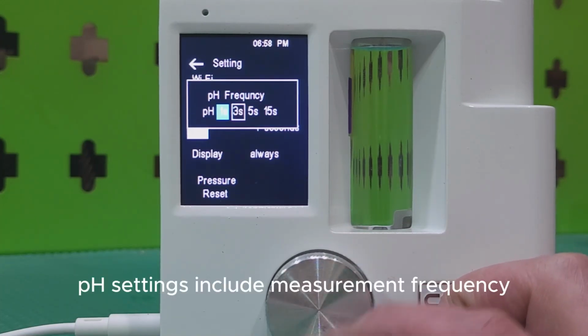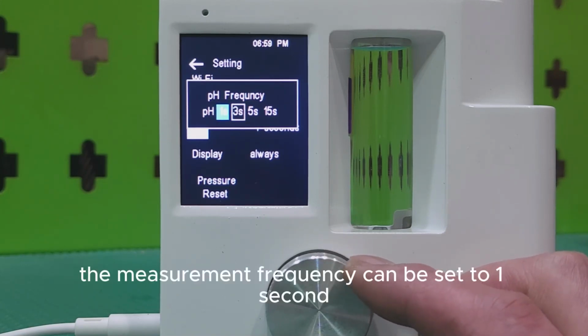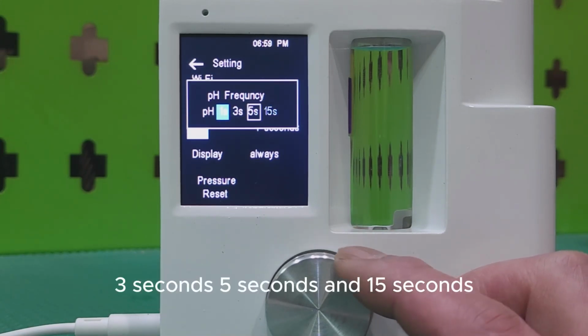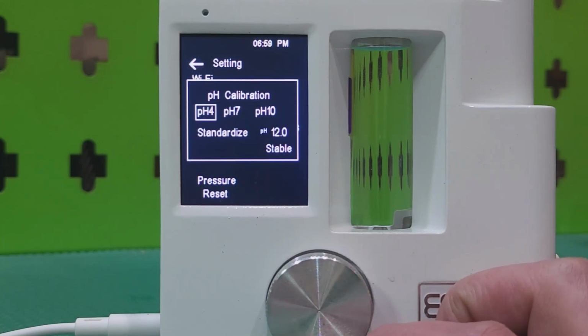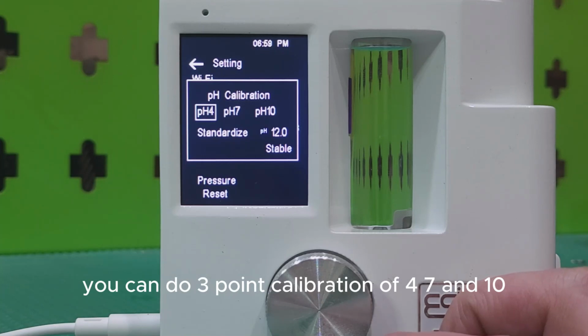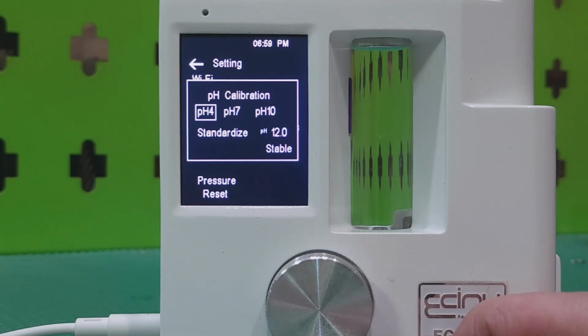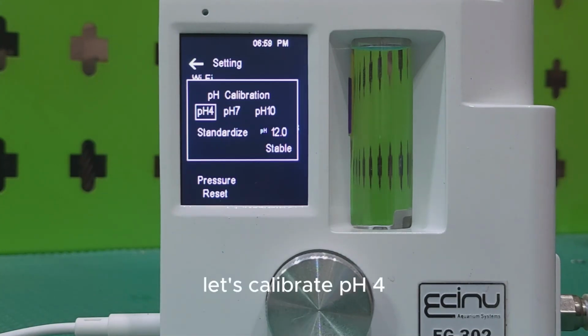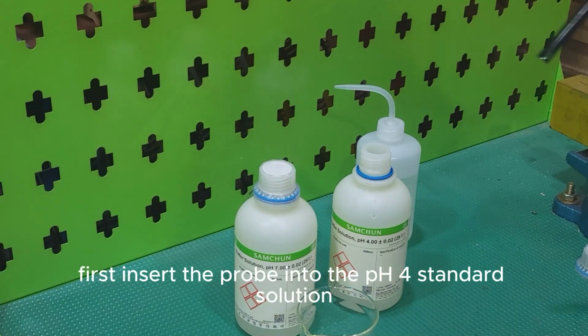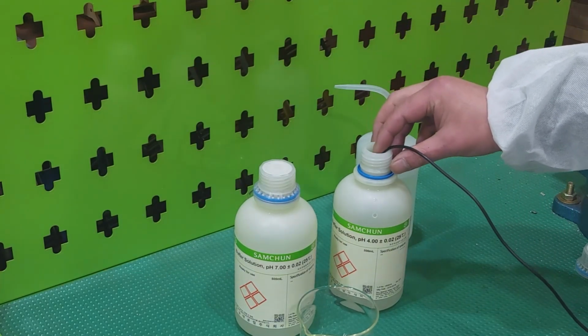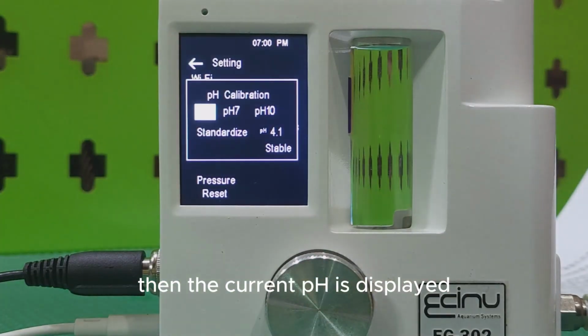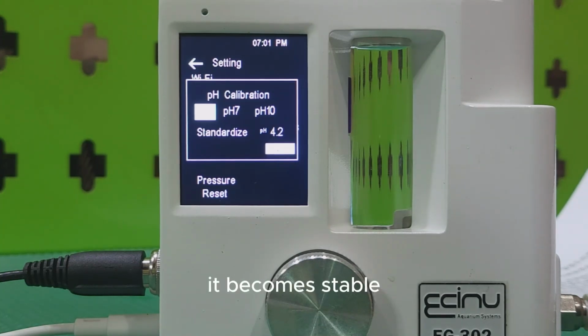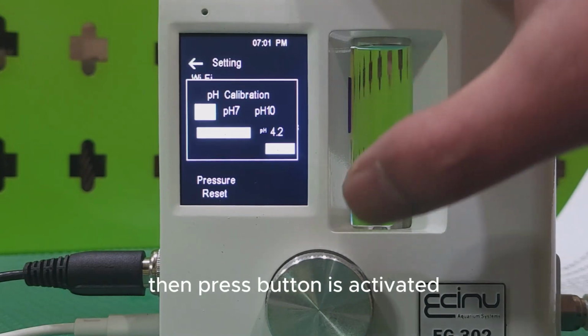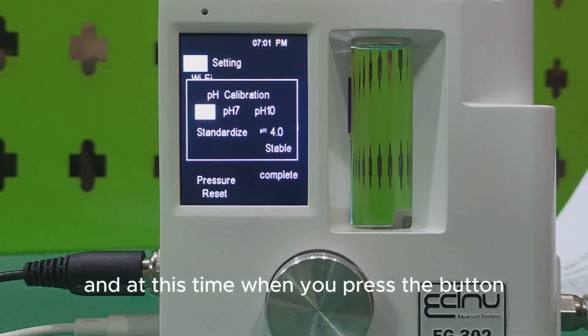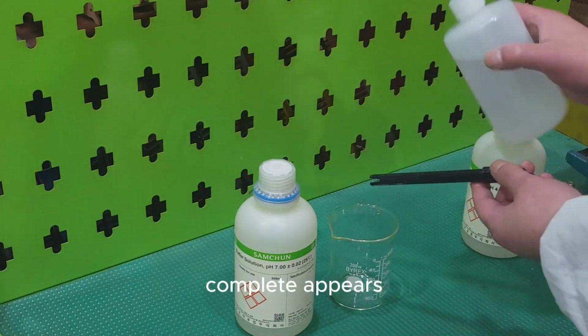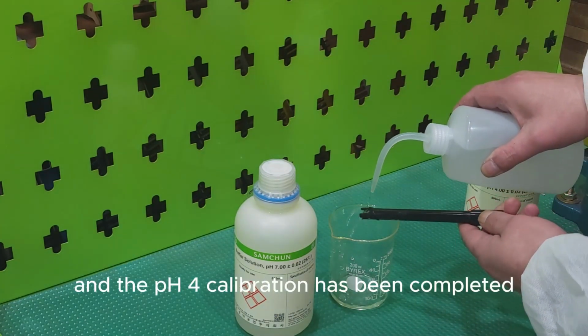pH settings include measurement frequency and calibration. The measurement frequency can be set to 1 second, 3 seconds, 5 seconds, and 15 seconds. Calibration: you can do 3-point calibration of 4, 7, and 10. You can use it by calibrating only 2 of them. Let's calibrate pH 4 first. Insert the probe into the pH 4 standard solution. Then the current pH is displayed, and when the pH has stabilized, "stable" appears. After "stable" appears, the button is activated, and when you press it, "complete" appears, and the pH 4 calibration has been completed.